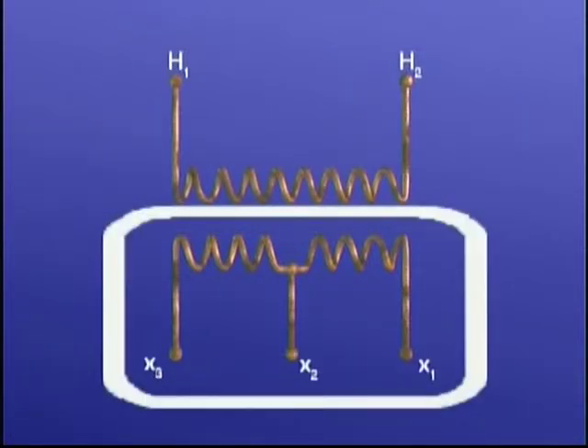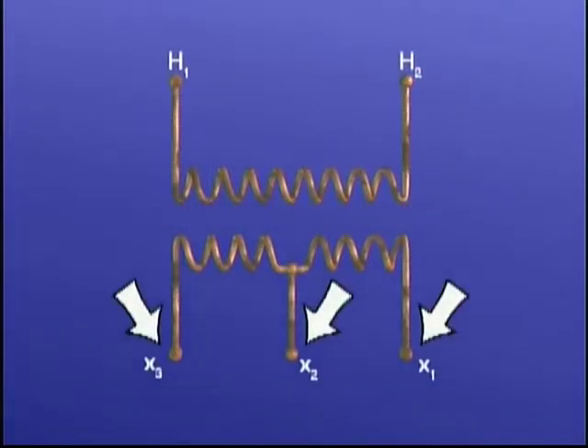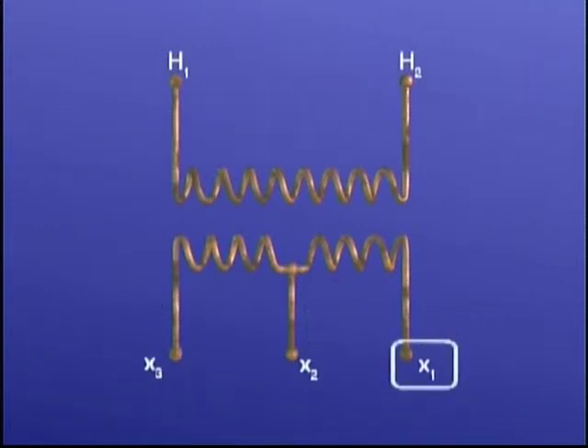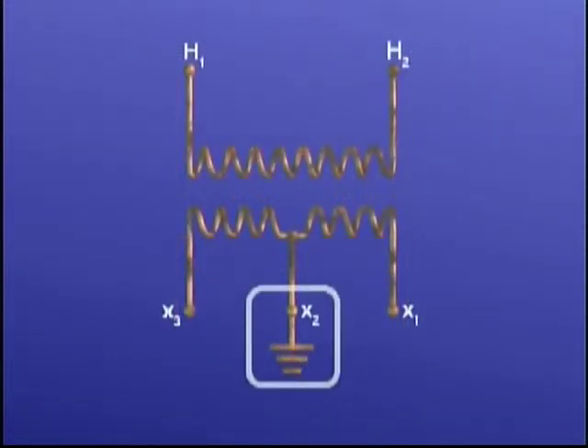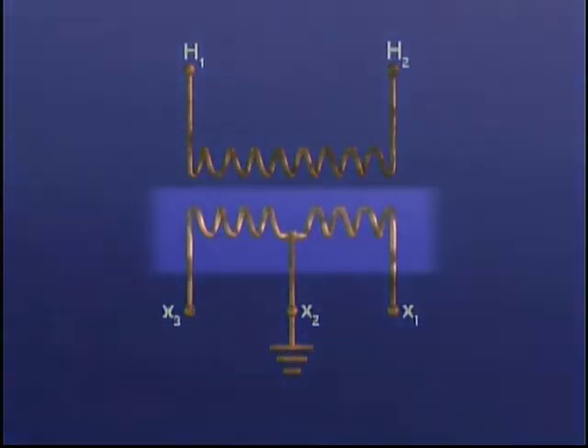Here are the two individual coils that make up the secondary winding of the transformer. In this example, there are three secondary bushings mounted on the unit. Inside the unit, an end of one of the secondary coils is connected to the X1 bushing. An end of the other secondary coil is connected to the X3 bushing. The remaining ends of both coils are joined together at the X2 bushing. In most cases, the X2 bushing is connected to ground. In this arrangement, the coils making up the secondary winding are in series.